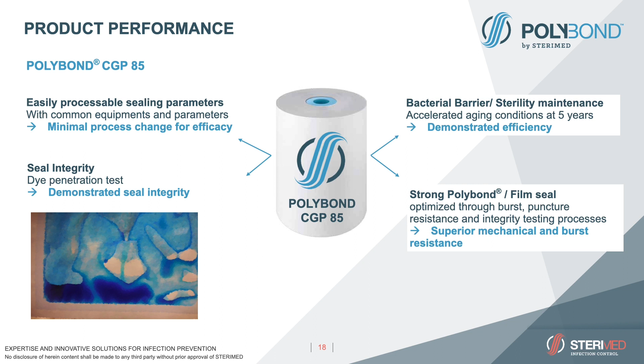So it works with common equipment and parameters, with minimal process changes for efficacy. We also have tested seal integrity with a dye penetration test, which has demonstrated seal integrity, as you can see in the picture. We also have tested bacterial barrier and sterility maintenance on the products. We have done 5-year accelerated aging conditions that have demonstrated efficacy.